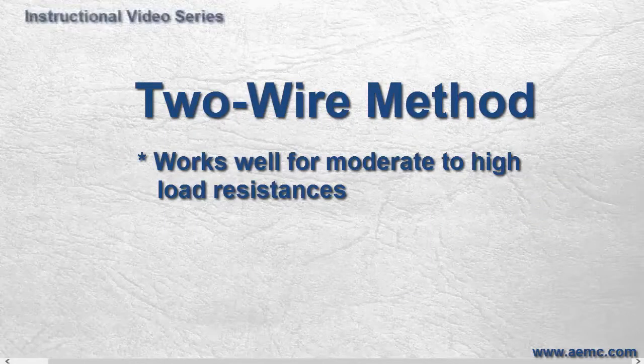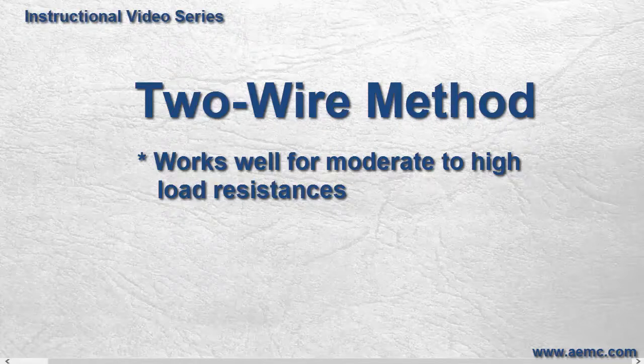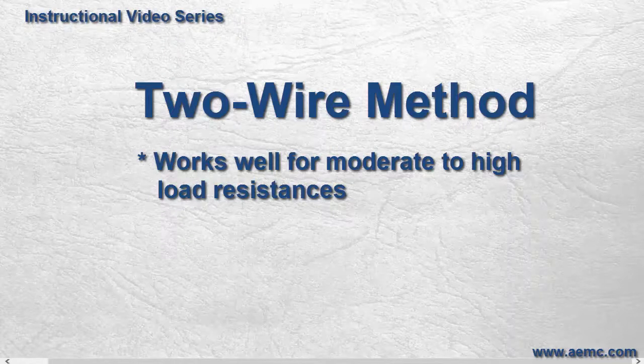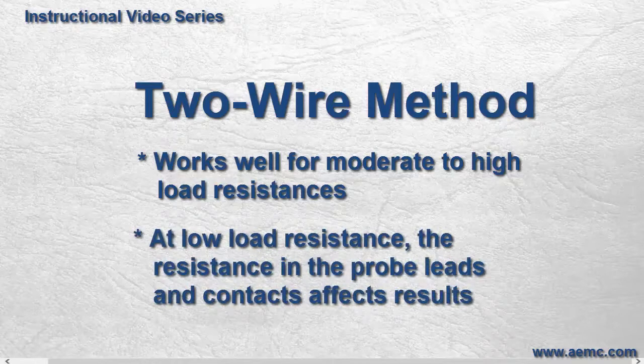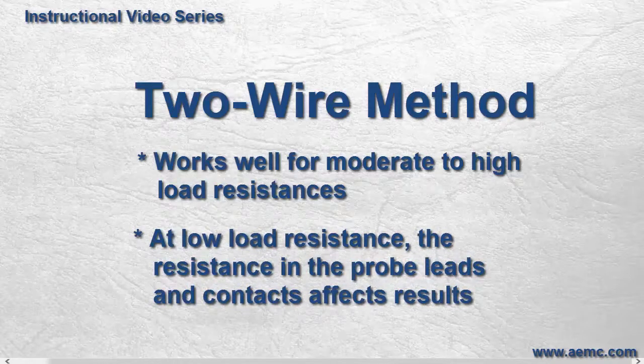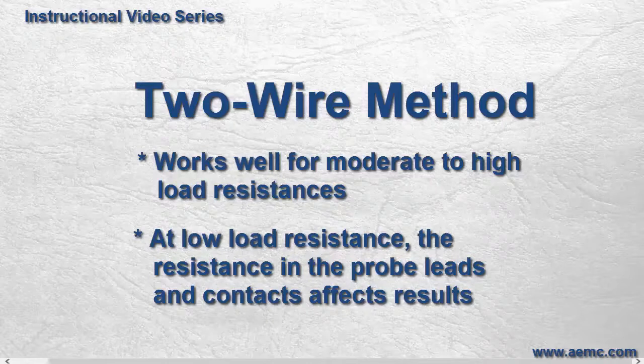The two-wire method works well for moderate to high load resistance or impedance. However, for very low load resistances, the resistance inherent in the probe wiring and contacts can contribute a significant percentage to the overall results, making the measurement of the test load resistance inaccurate.